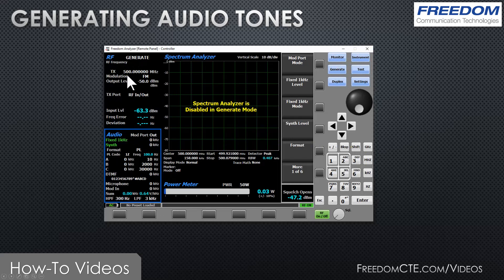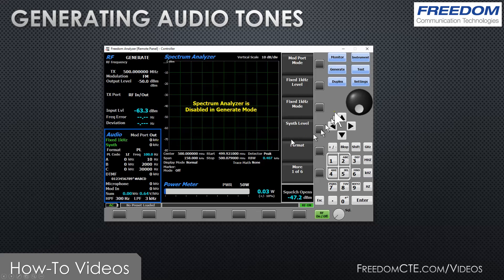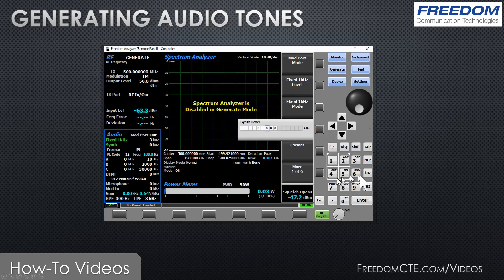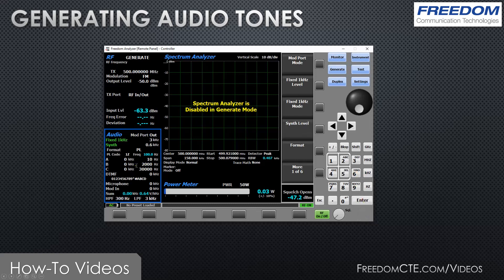We're going to go to generate mode. Pressing the blue generate button, now we are generating a carrier at 500 megahertz. Here's our output level. In the audio zone you can see that my fixed one kilohertz and my synthesizer are still on, however their levels have not been defined in generate mode. Notice now the units are in kilohertz rather than volts. Fixed one kilohertz level — let's put a three kilohertz deviation, assuming this is a 25 kilohertz channel signal. We're going to set our synth level to 0.6 kilohertz. Now I am modulating the carrier with both a one kilohertz tone at three kilohertz deviation and a 100 hertz PL tone at 0.6 kilohertz deviation.